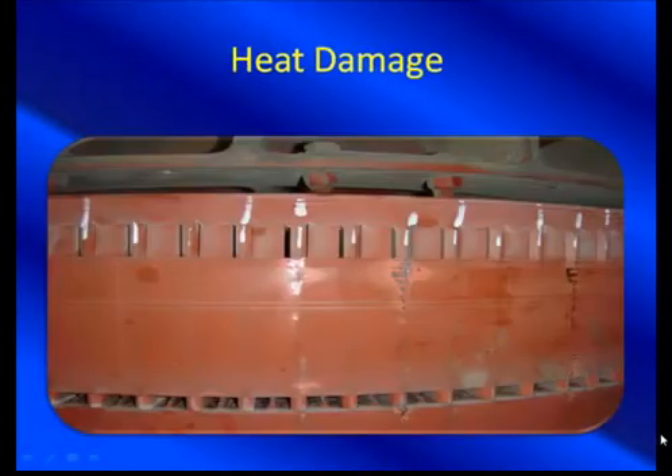Normally you don't have white lines on your rotor unless something's happened — a little bit of heat going on there. Each of those white lines is on a bar itself, and that bar travels the length of that rotor underneath the individual laminations that are burning up there. Current through a broken bar doesn't like to flow very well, so it tries to find another way to get from one end of the rotor to the other, traveling along the iron. Even though those are supposed to be insulated from each other, current will find a way and create a lot of heat. And this rotor is very close — just a few millimeters away from the stator. If it has a lot of heat coming out of the rotor, you could potentially be having some trouble with that stator too.